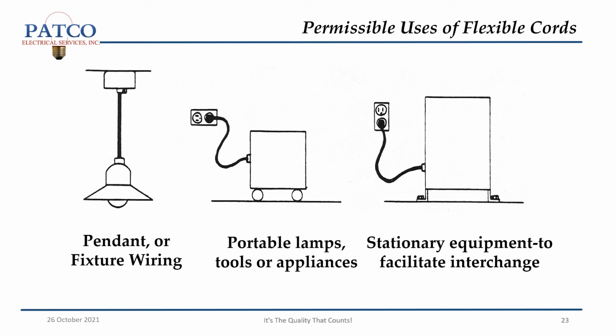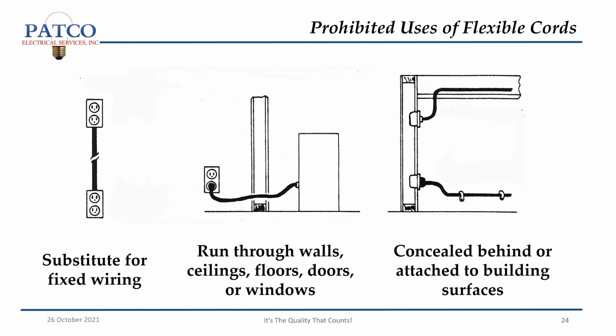Permissible uses of flexible cords: pendant or fixture wiring, portable lamps, tools or appliances, and stationary equipment to facilitate interchange. Prohibited uses of flexible cords: you can't substitute them for fixed wiring, you cannot run them through walls, ceilings, floors, doors, or windows, and you can't conceal them behind or attach them to building surfaces.